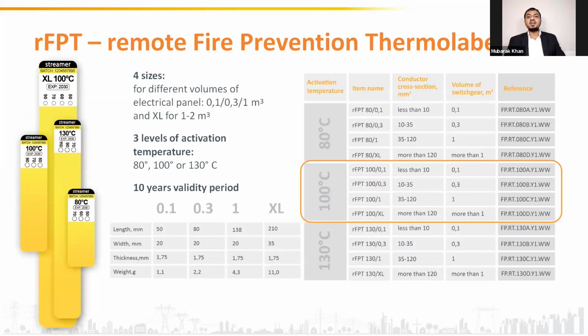Now these stickers come in various sizes and temperatures. We have small stickers for smaller cabinets and smaller conductor cross section. We have bigger stickers for bigger cabinets with bigger conductor cross section. Again, there is a selection of stickers based on the required temperature range. You can have stickers of 80 degrees Celsius or 100 degrees Celsius or 130 degrees Celsius depending on the application. As explained before also, for the Indian scenario in electrical applications, 100 degrees Celsius is the most optimum temperature to get an alarm.